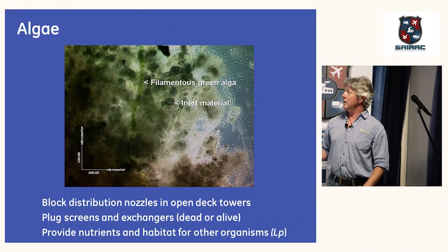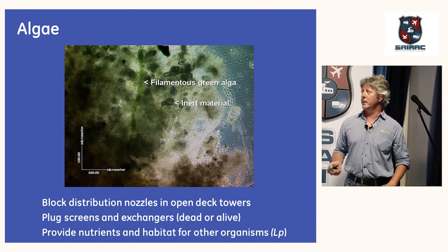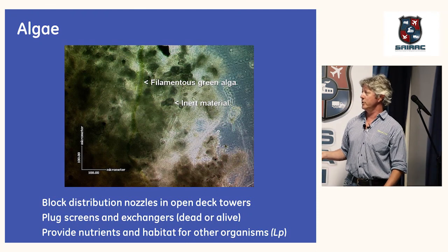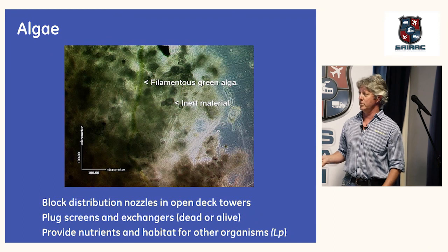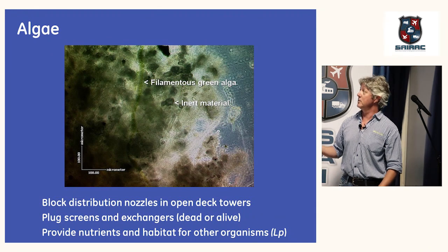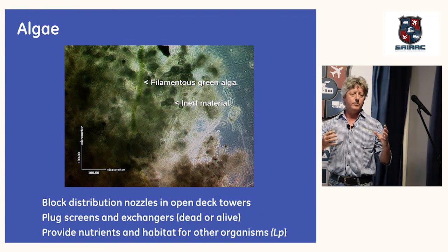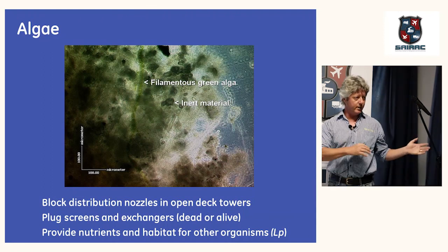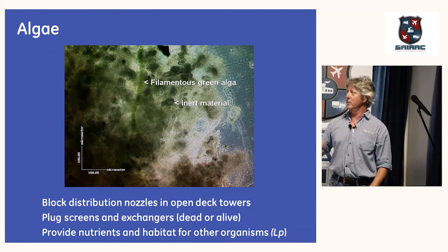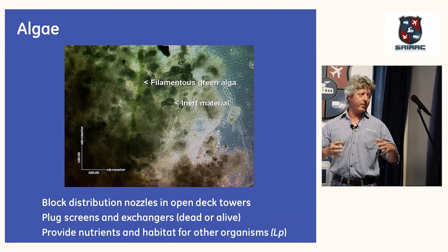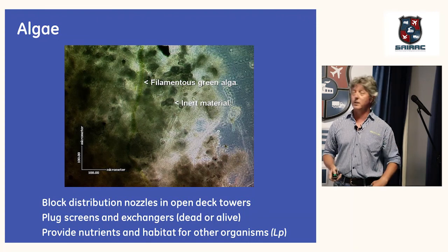Okay, what algae does, or what any of these slime formers actually do, is they can block your distribution nozzles in open deck towers, plug screens and exchangers, and provide nutrients and habitat for other organisms to grow. Okay, so you can see these are inert material, algae growing there. Any kind of dust or particle that gets recirculated can get entrapped in the slime layer, and that will just add to your slime layer getting thicker and stronger at the end of the day.